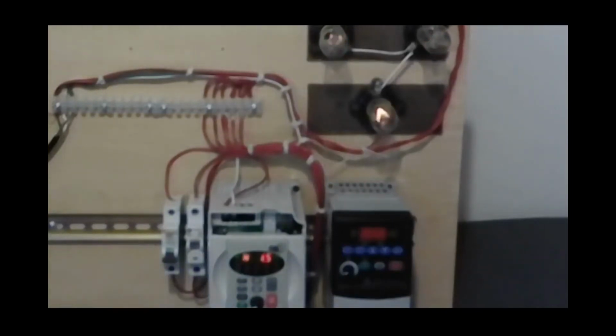Drives are pretty simple things, but they are all electronics. Inside the backs of these drives, you've got some pretty large circuit boards with a lot of components on them. There's large capacitors in there. There's conversion circuits. It's also basically electronics. Now, some of the problems we have with drives is they fail. One thing that will cause failure on the drive is on the input circuit. Power coming into the drive, if this drive receives a large voltage spike or a large transient voltage, that transient voltage can kill the drive.